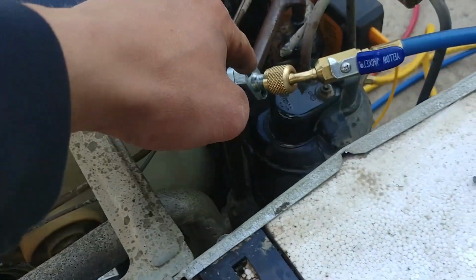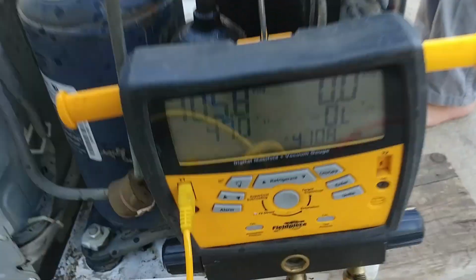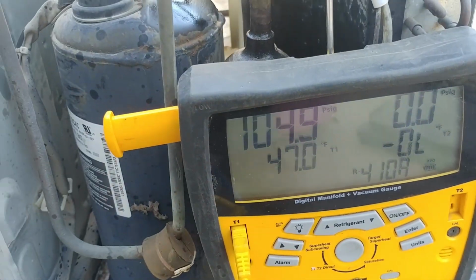So we added a line tap right here on the low side, and we ended up adding in about 14 ounces. And now this is the air temperature right here, the literal air temperature - 47 degrees, so that's really nice.